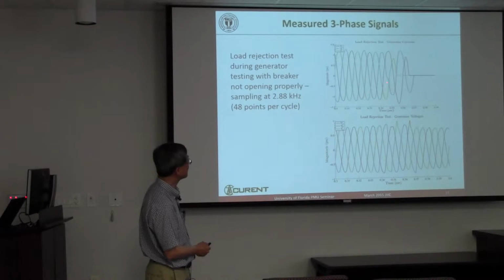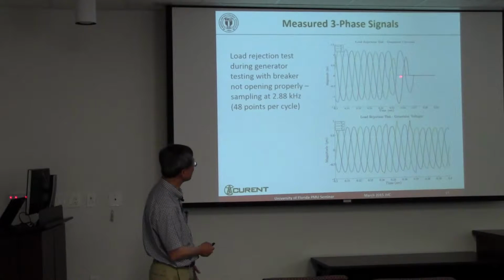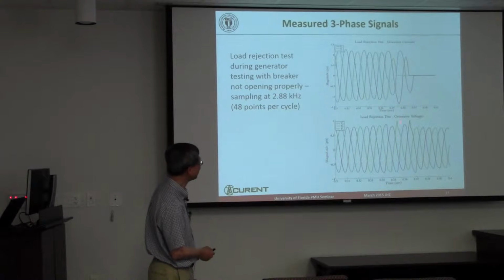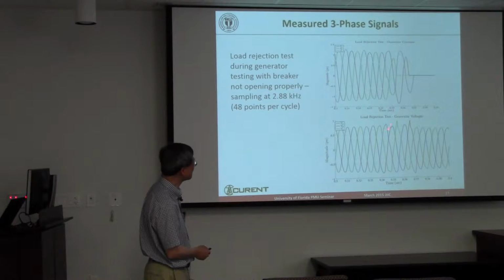What happened was that this circuit breaker was actually damaged. At this point they tried to open it, it was not successful, so it continued through. Then there's another point they tried to open, it didn't work. Then on the next cycle, at the zero crossing, it opened successfully. In between, on the voltage, you can actually see spikes.